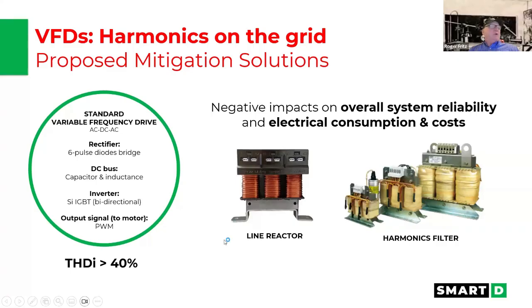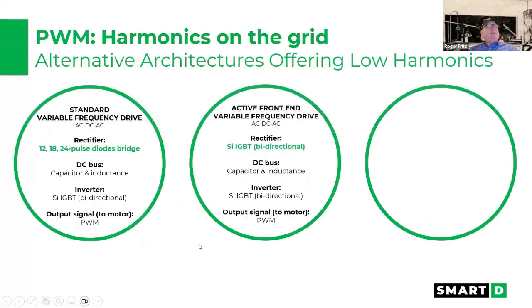So then they've come forward and they've actually started requiring more line reactors and then these harmonic filters on the output. So you put the line reactor on the front that helps mitigate some of this harmonic content. And then you've got the output, which is basically also trying to mitigate some of the content. These are all non-active. So again, what's happening is that all that frequency that's out there, power doesn't go away. It goes somewhere. And most of the time, what they're trying to do is isolate it off the ground and feed it into the network.